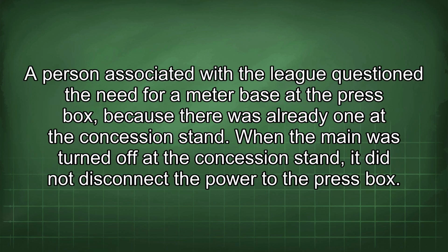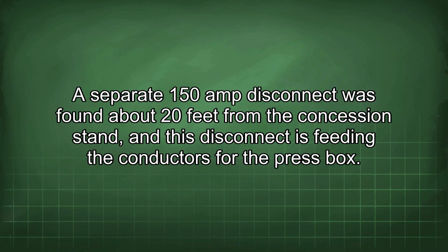A person associated with the league questioned the need for a meter base at the press box because there was already one at the concession stand. When the main was turned off at the concession stand, it did not disconnect the power to the press box. A separate 150 amp disconnect was found about 20 feet from the concession stand, and this disconnect is feeding the conductors for the press box.